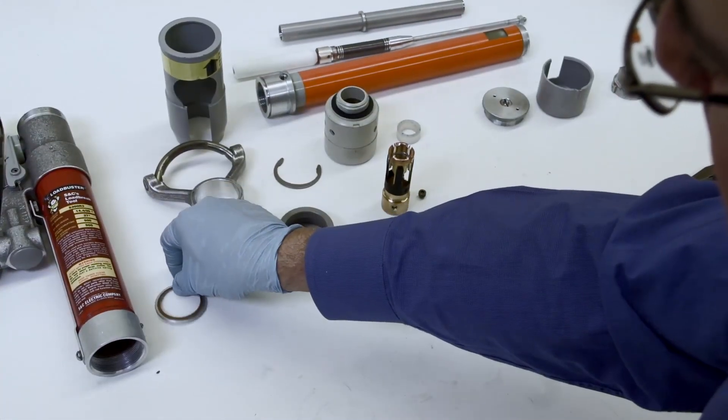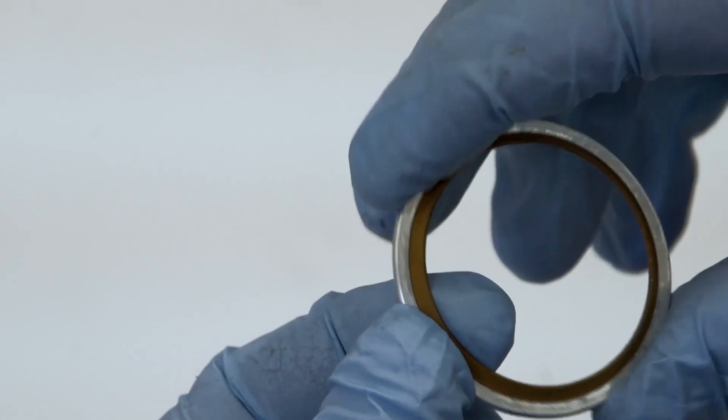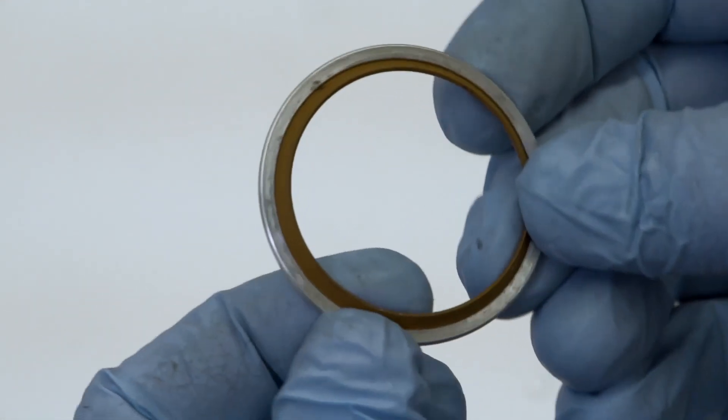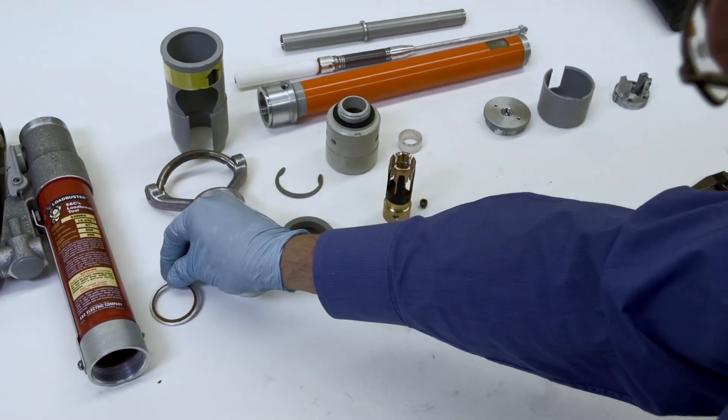Then examine the inner tube seal to make sure the seal is round, the gasket material is free from cracks and is even in shape. Replace the seal if necessary.